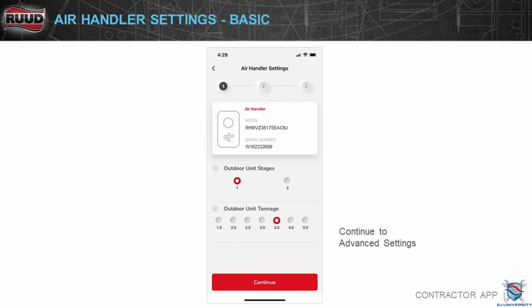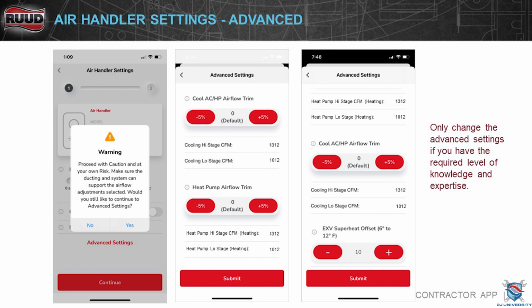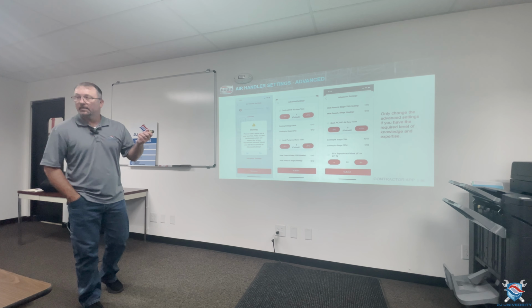Still continuing through advanced settings. A lot of trim settings in this. So if you go into an advanced setting, you can do cool airflow trim. You can increase or decrease it by 5%. Heat pump airflow trim, you can also do it on the heating side as well. Once again, here's their EXV superheat offset. Does give you CFM ratings on high and low stage. I like that they put that in there.